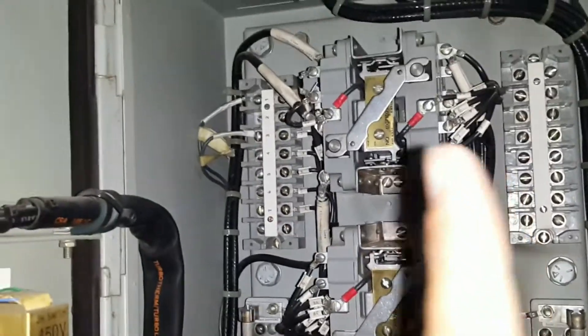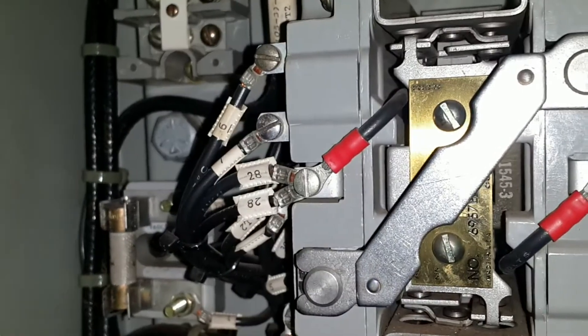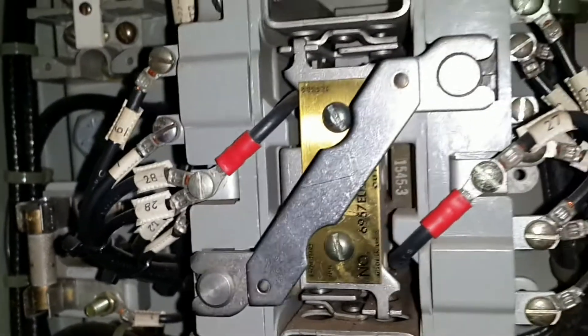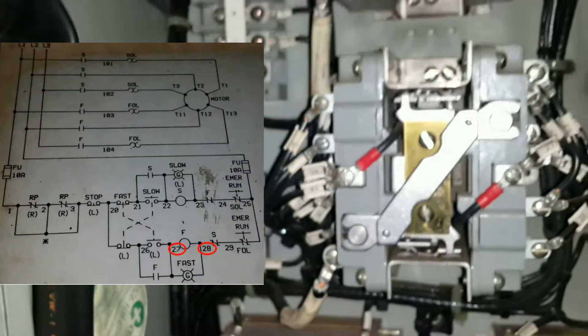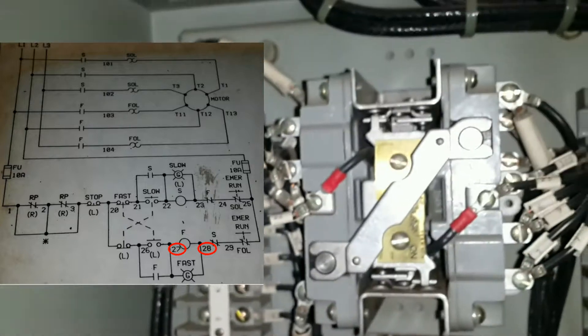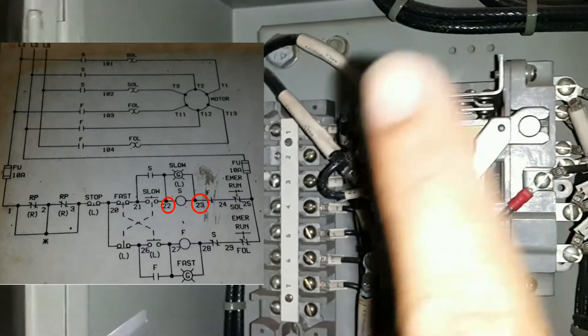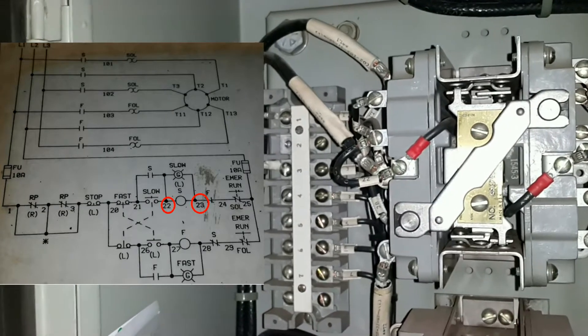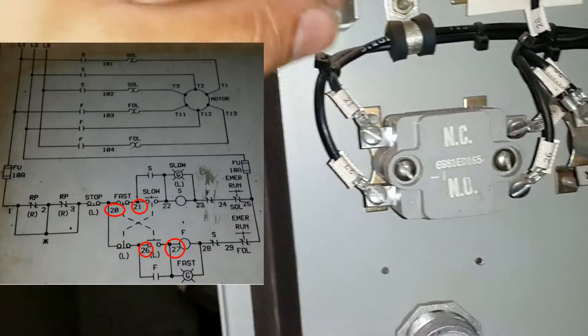If you look at the figure really close, I got connections over there, 27 and 28, which is for our fast speed. And then this coil over here gets 23 and 22, so that's our slow speed contactor. Our switches: this switch over here, this one got 21, then the way they're hiding is 20, 26, and 27.